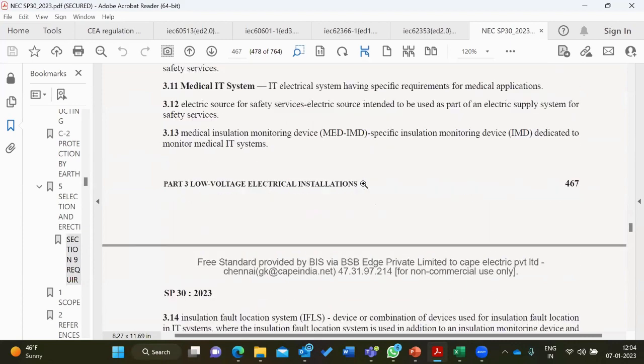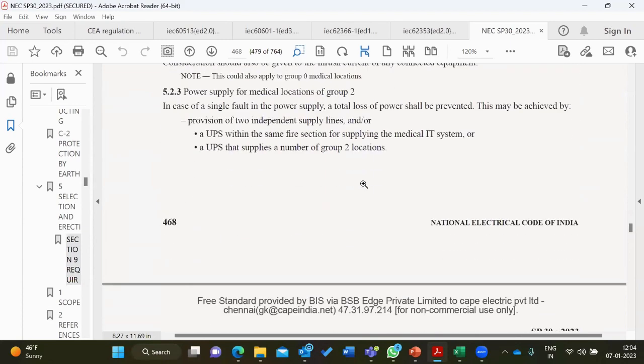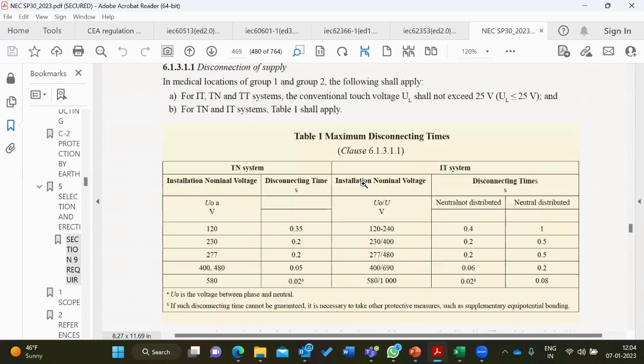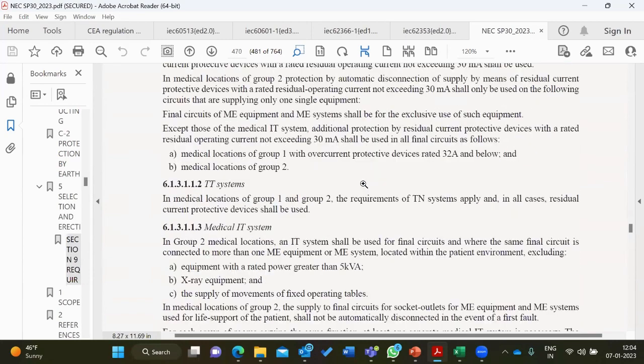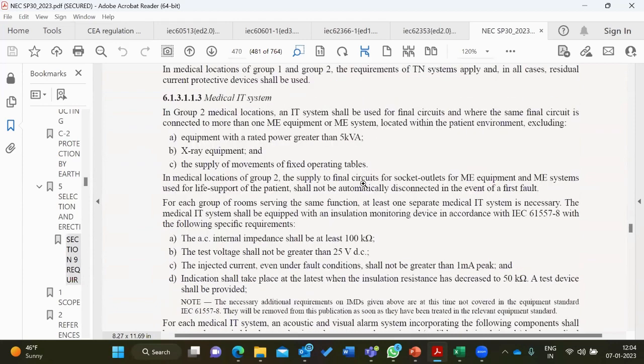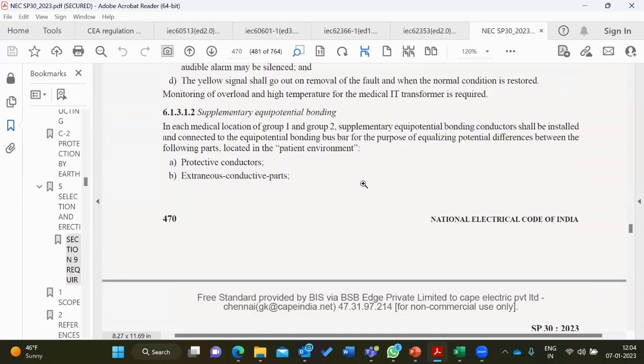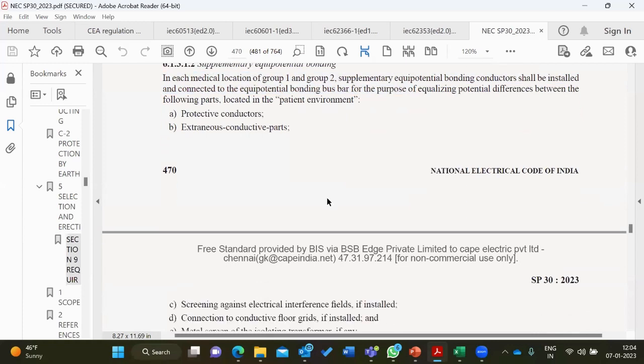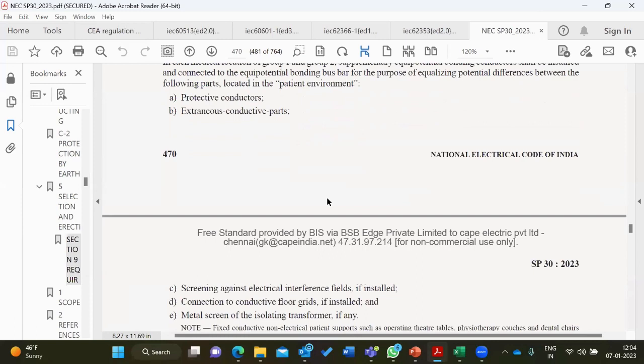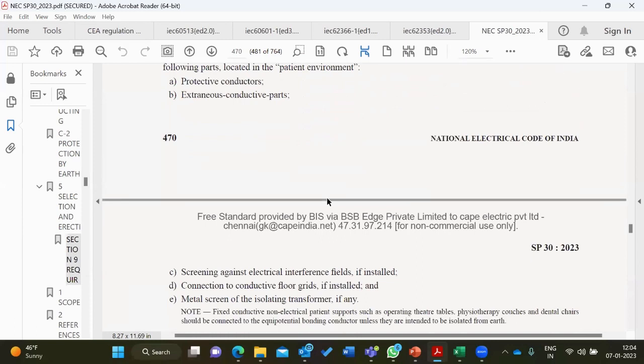And here, there are so many requirements. I will just show you the requirement of the earthing alone. It is called supplementary equipotential bonding. Supplementary equipotential bonding means in a medical environment, all the metallic objects in that area must be interconnected in such a way that, you can see here, in medical location group 1 and group 2, supplementary equipotential bonding conductors shall be installed and connected to the equipotential bonding bar. So what the standard says is you must interconnect everything together so that between two equipment, the resistance of the connection must be less than 100 milliohm. This is a technical requirement.